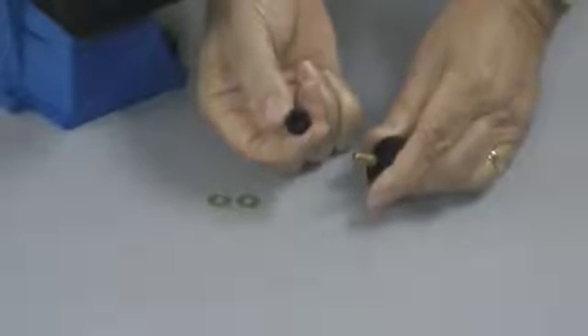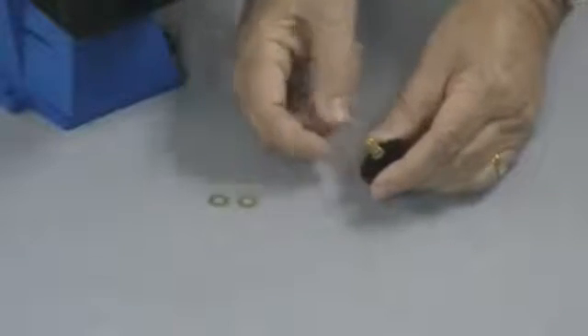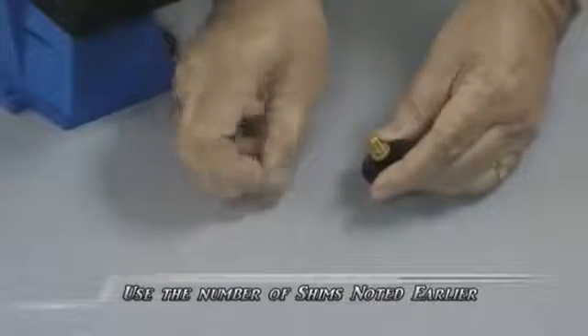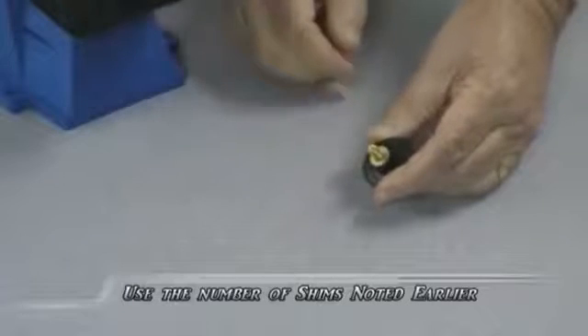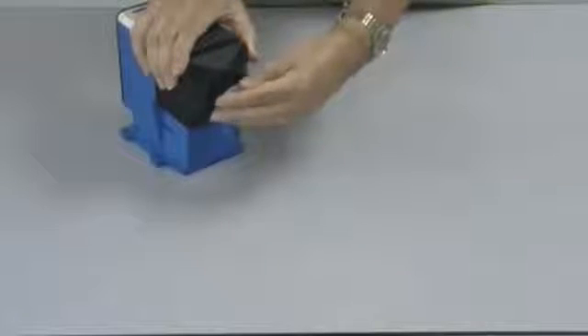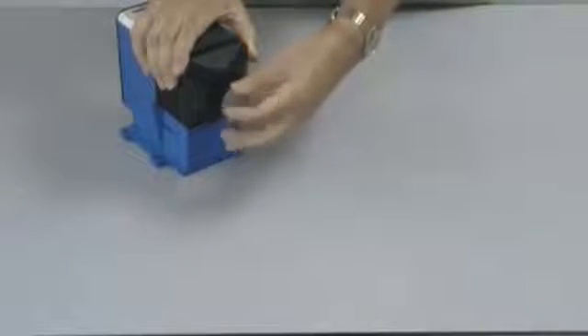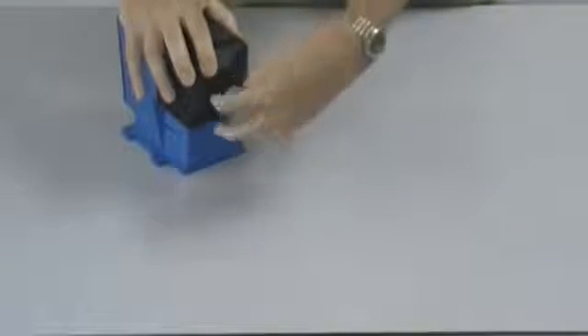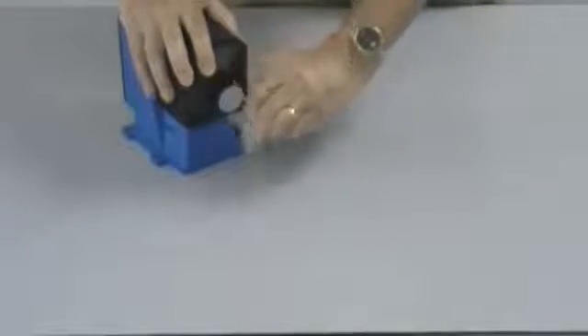The deflection plate has a radius on one side. That radius goes against the diaphragm. And the brass shims then go behind the deflection plate. Then the diaphragm assembly is threaded on to the end of the shaft, assuring that the adapter plate is in position all the way back. Turn the diaphragm until it stops.